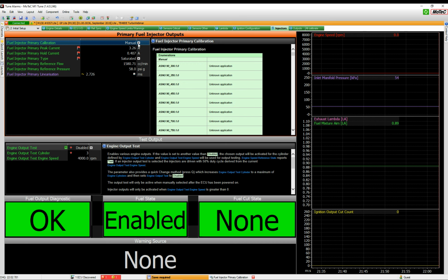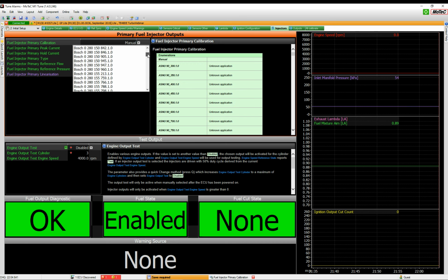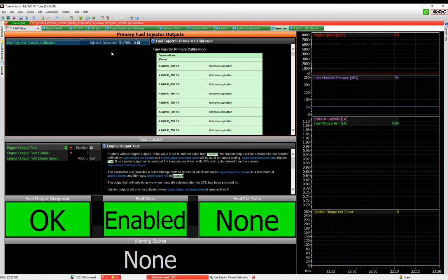and we'll just click back to, well, we can go for that Siemens Deka or any injector. ID 1700s, where are they? They're not here. Yes, they are. There we go. So these are the Injector Dynamics 1700s, which are quite popular now. Alright, so as you can see, two things have happened. One, all the setup's now gone because that's all included in the calibration, so you don't need to worry about peak and holds or saturated or minimum volumes or anything. It's all gone away because it's all contained in this calibration.